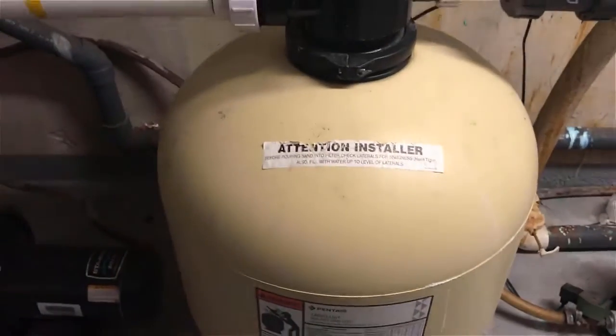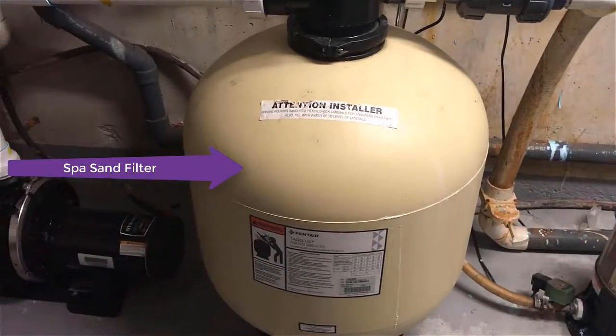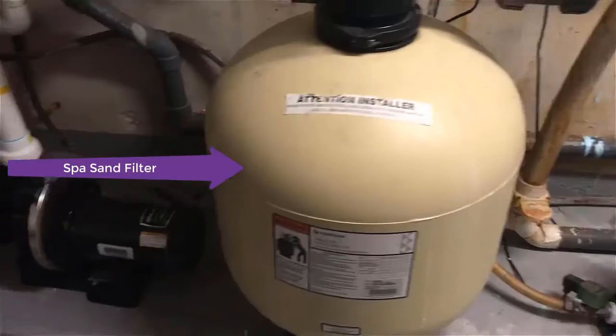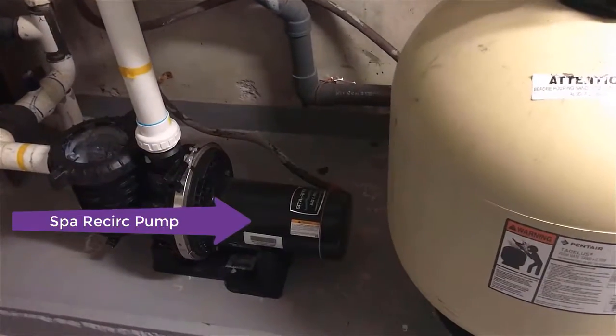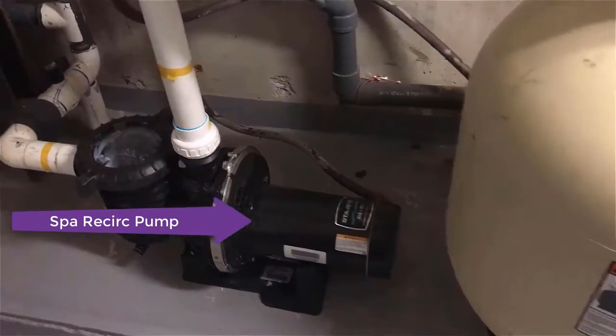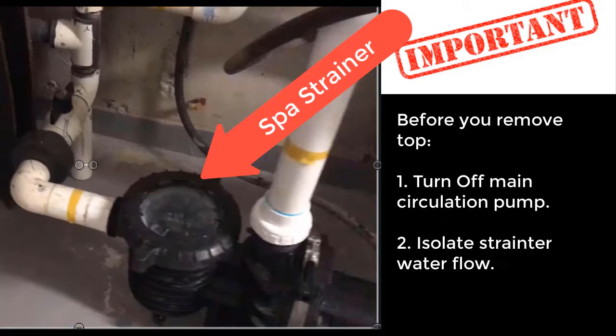So we're in the pool chemical room now, and this is the spa filter. It's the smaller of the two. And beside the spa filter, there's the spa recirculation pump. Next to that is a strainer that filters out any large particles before they get into the sand filter, like lint or debris. This strainer should be checked every couple of weeks and cleaned out, otherwise the debris can affect the flow of water that goes through the pump and sand filter, causing the spa to become milky and dirty.